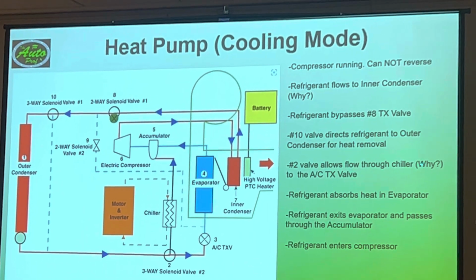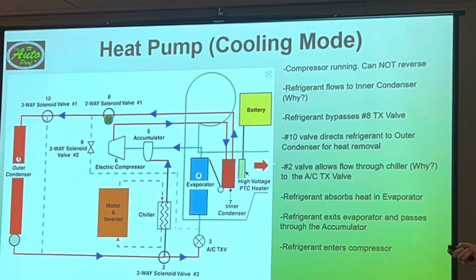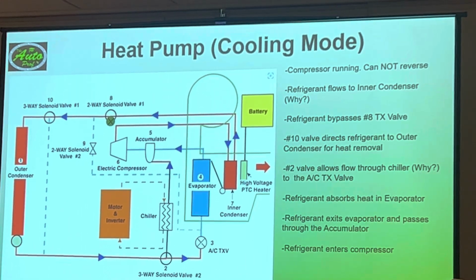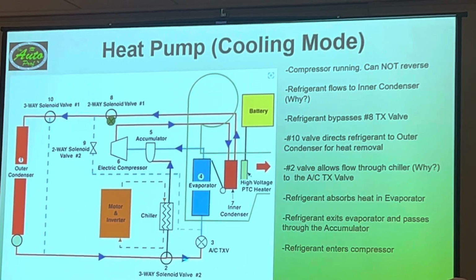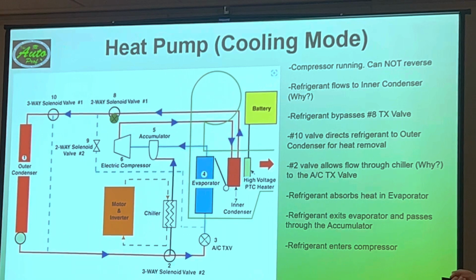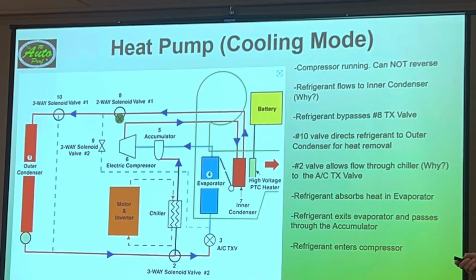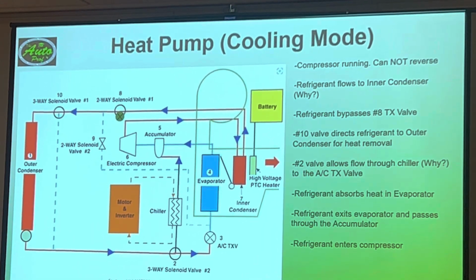So number 2 valve allows flow through the chiller, okay, and to the thermostatic expansion valve, so that guy's flowing through and diverting there, and then our refrigerant comes through the expansion valve, and we cool off our normal evaporator like we used to.